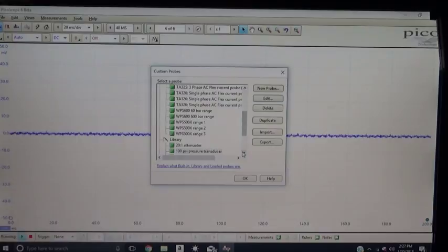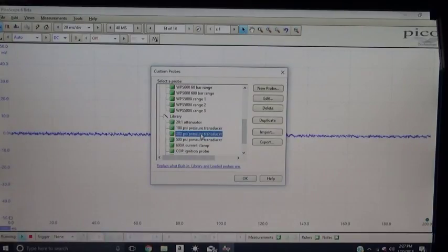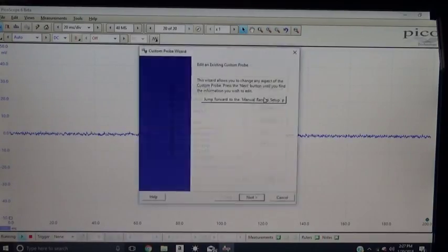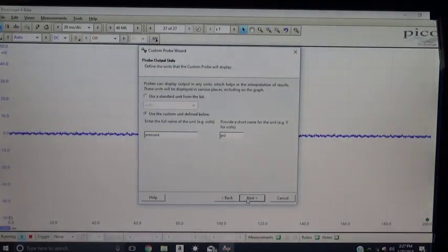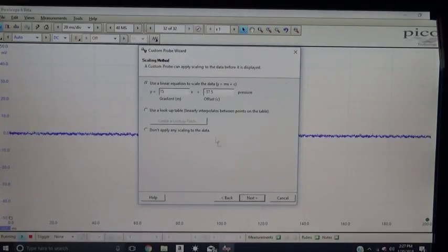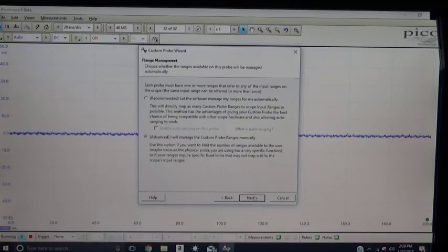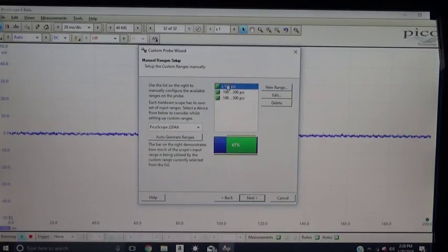Okay, the next one we'll go to a 300 pressure transducer. Go to next, again you're going to do pressure and psi. Next again, on this one we're going to put 75 in gradient, and the offset is going to be minus 37.5. Just type those numbers in and you'll be okay for 300 psi. Advanced, I'm sorry, I did 100, 200, and 300 psi range, and that's it.